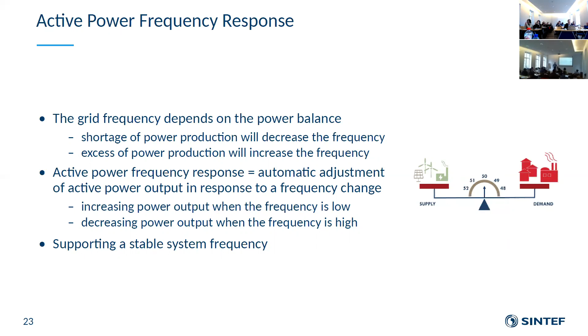The grid codes split into two parts, which is good, especially for wind power - it's very relevant: the over-frequency and under-frequency parts. For over-frequency, we have too much power, and this is something wind power can easily handle, because we just need to reduce the output if necessary. In theory, this gives economic losses, because once you reduce, you extract less power.